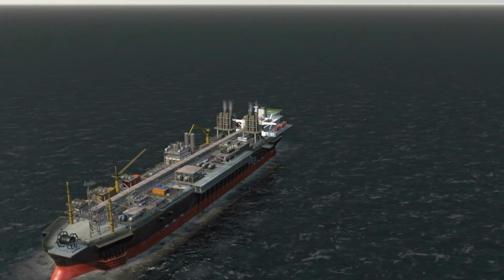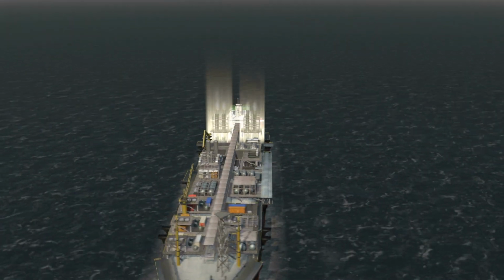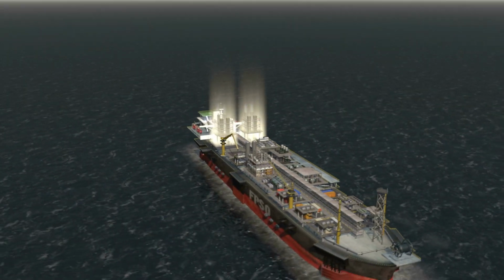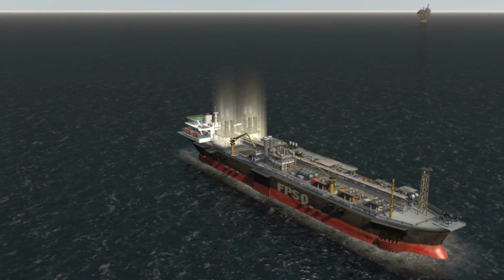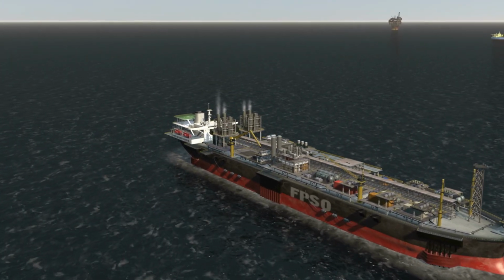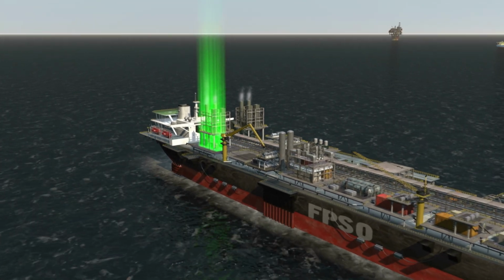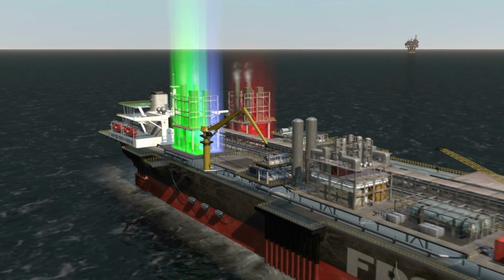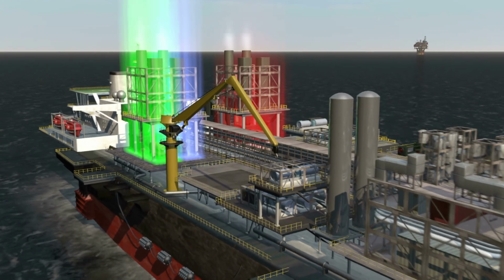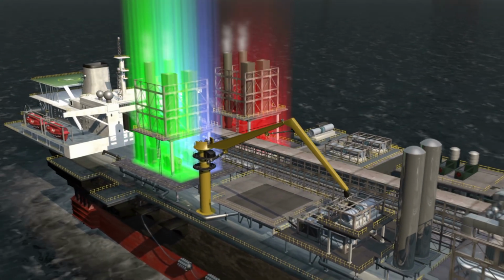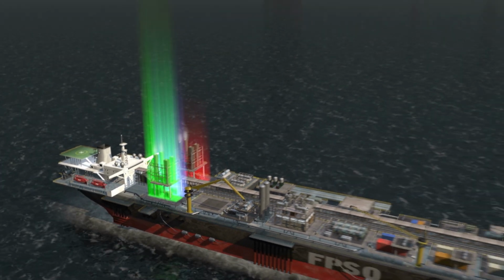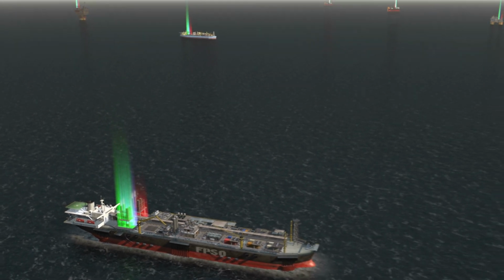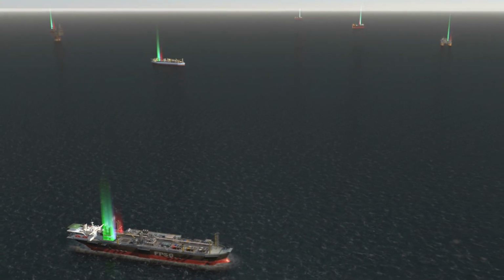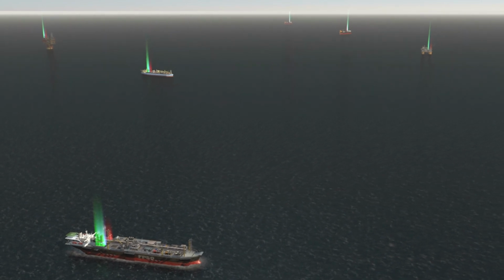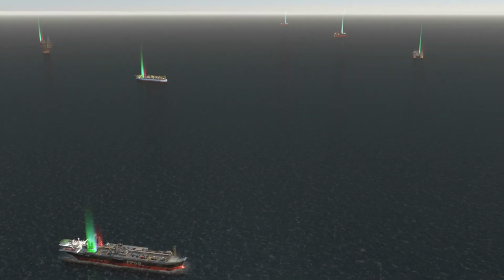At present, to meet the offshore power demand, conventional FPSOs are fitted with massive power generation equipment. The power arrangement typically consists of 4 gas turbine units, one used at full capacity and the remaining throttled to meet the varying demand or otherwise reserved for redundancy. This redundant capacity is necessary to meet the high availability requirements of each independent vessel. However, operating gas turbines at low efficiency results in high fuel consumption and elevated emissions.